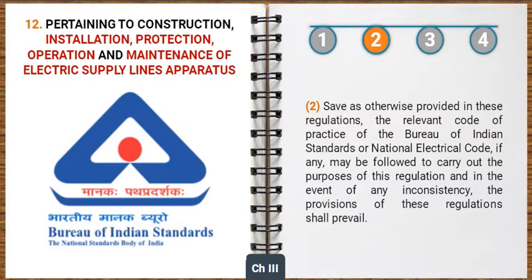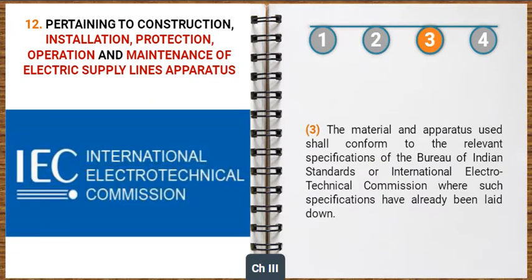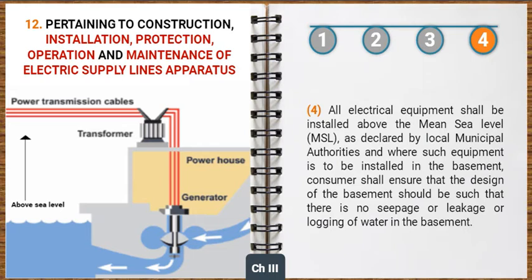Save as otherwise provided in these regulations, the relevant code of practice of the Bureau of Indian Standards or National Electrical Code, if any, may be followed. In the event of any inconsistency, the provisions of these regulations shall prevail. The material and apparatus used shall conform to the relevant specifications of the Bureau of Indian Standards or International Electrotechnical Commission. All electrical equipment shall be installed above the mean sea level (MSL) as declared by local municipal authorities, and where such equipment is to be installed in the basement, the consumer shall ensure that the design of the basement is such that there is no seepage or leakage or logging of water.